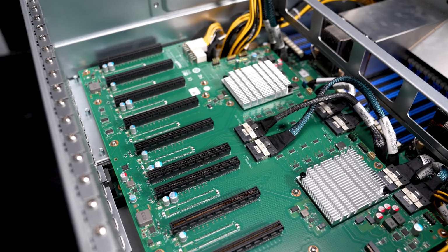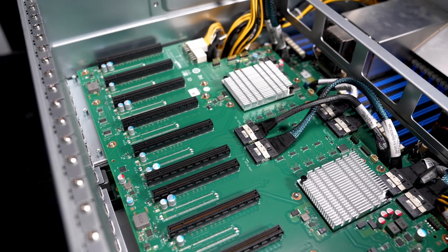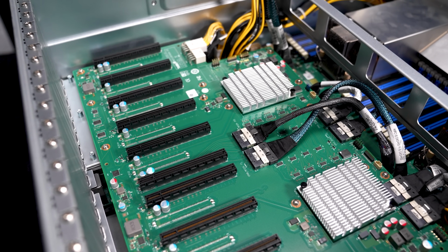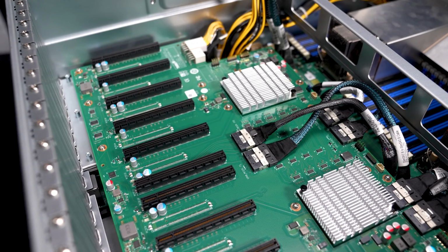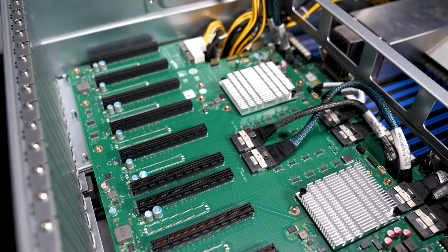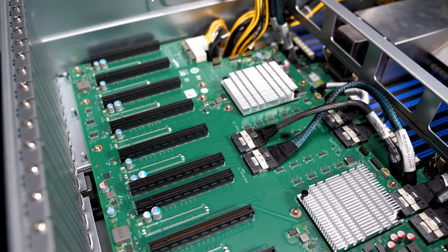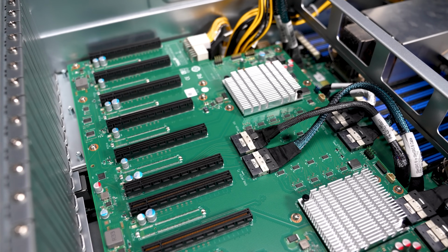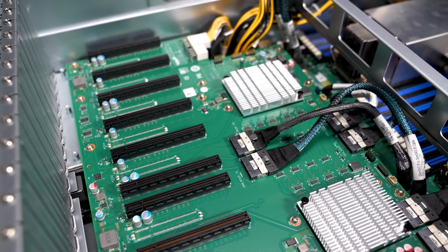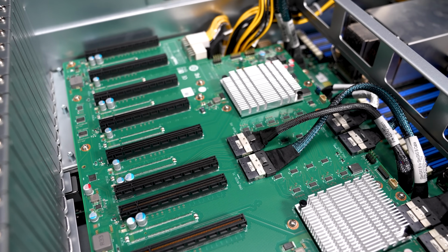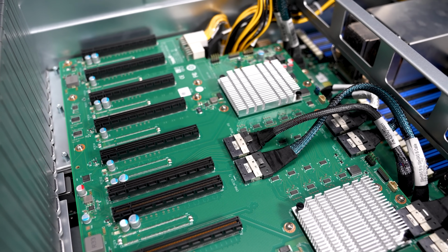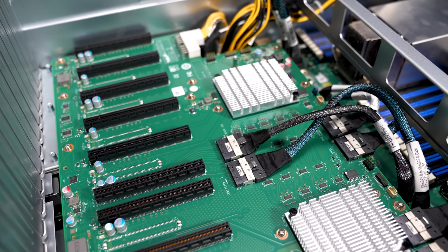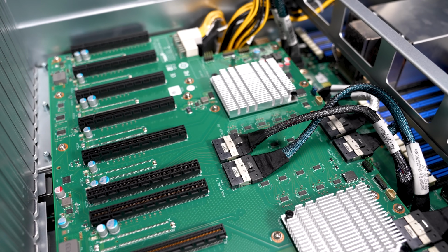I will just note real quick that we did have to do a little bit of blocking of airflow here, because we had a really early unit and we didn't have the block for 8 GPUs. Usually in the middle of these systems, you'll have a little airflow guide, so that if you only have 8 GPUs, there'll be an airflow guide to block off some of this middle section. That way you can divert airflow where it needs to go. Some companies will actually do it on the side, but it's something you have to do to make sure any GPU system functions properly. You have to make sure that you have the right blocking versus GPUs and accelerators that are open slots for airflow to go through. So just a mention of that real quick, but let's keep going.